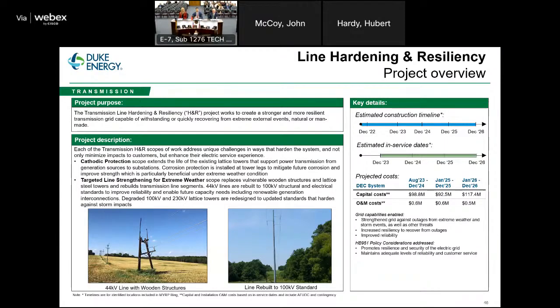Although at this time we don't have any discrete plan to eliminate the 44 kV system due to its widespread nature, through our rebuild program we're allowing that as capacity needs dictate, we can modify the substation equipment at either end of the line and energize at the higher voltage level. A lot of the 44 kV system serves manufacturing and industrial customers whose equipment is designed to receive that voltage, so we generally wouldn't obligate them to upgrade. That's significantly down the road.